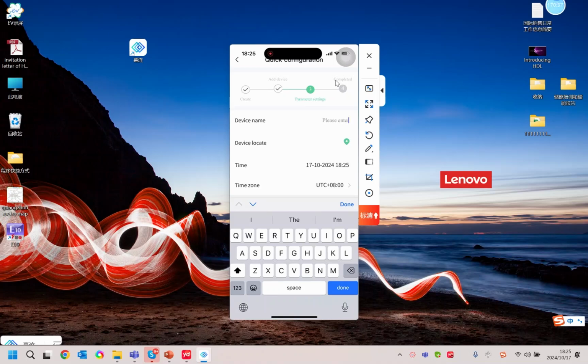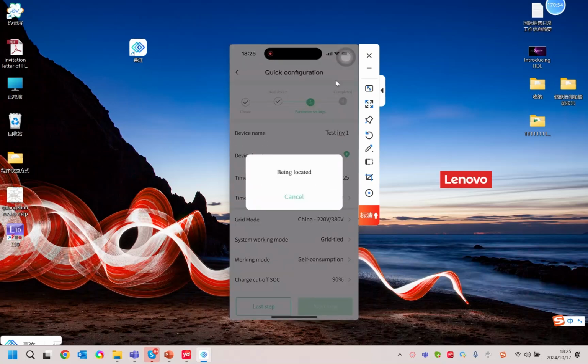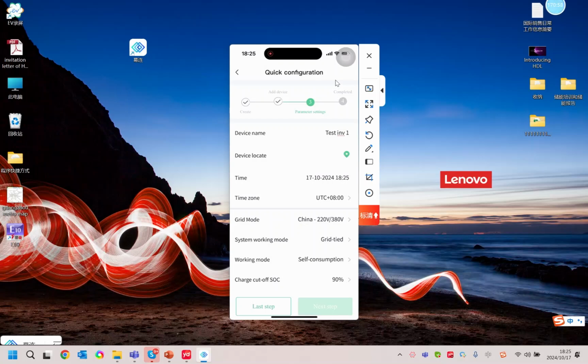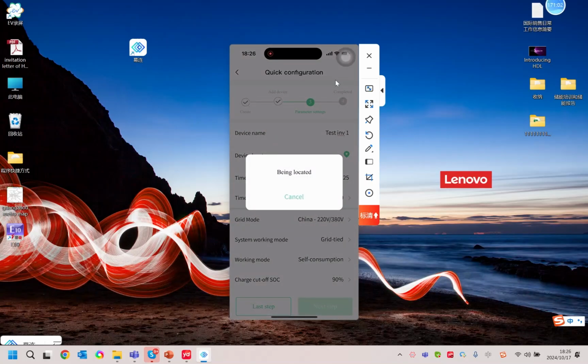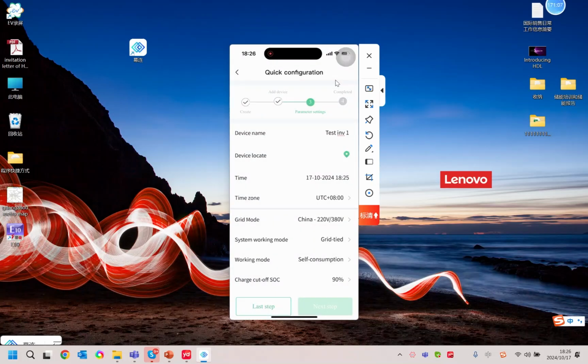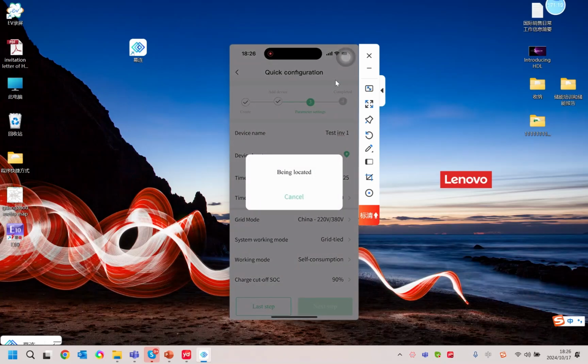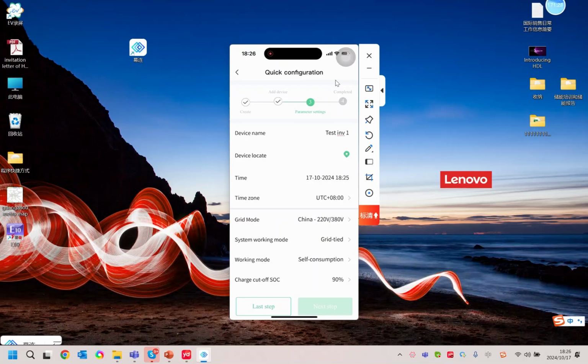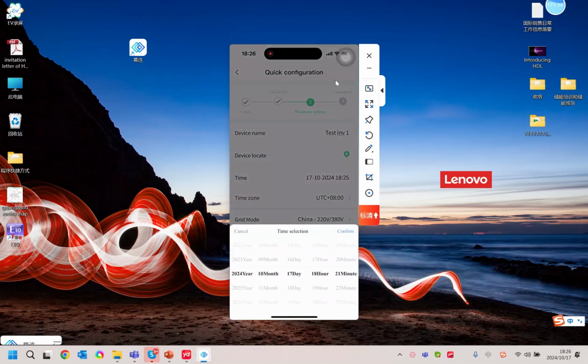We need to edit and set the parameters of the inverter here. So device name, okay, test 1, okay, the same. This device locate, for example, is used to locate the hardware. If you installed more than one inverter there, and you want to find which one you are configuring, you put this one, it will broadcast to the inverter, and all the LED light indicators in this inverter will flash, so you know which one you are configuring.